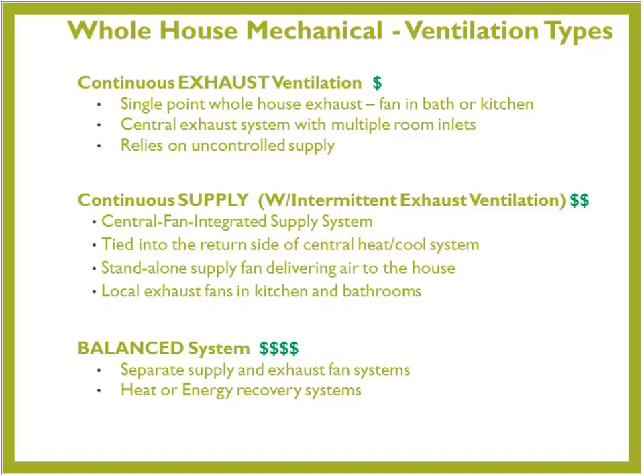But this is a ventilation approach where we're taking equal amounts of air from outside and bringing it into the building, while we're exhausting an equal amount of air. So where exhaust only might create a little bit of negative pressure, and supply might create a little bit of positive pressure, in a balanced system we're going to be pressure neutral, because ideally, in a perfect install, we've got the same amount of air, let's say 100 CFM, exhausting from the building and 100 CFM being supplied to the building at the same time. So we're not creating any negative or positive pressure with the balanced approach.